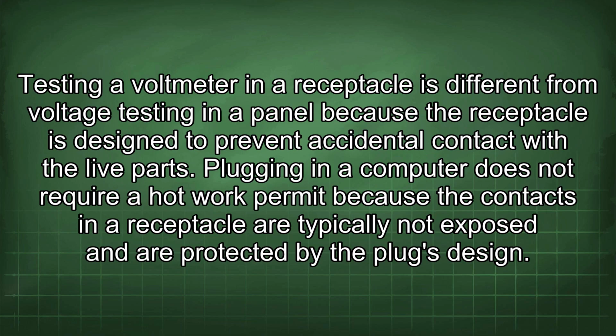Testing a voltmeter in a receptacle is different from voltage testing in a panel because the receptacle is designed to prevent accidental contact with the live parts. Plugging in a computer does not require a hot work permit because the contacts in a receptacle are typically not exposed and are protected by the plug's design.